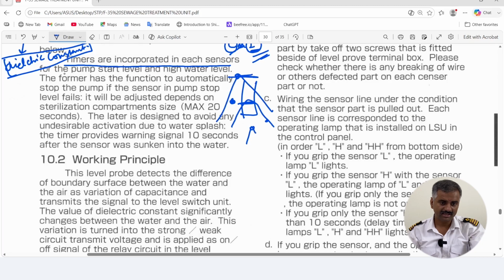To avoid this, pump starting at high level and high water level, the timers are incorporated to start the pump at high level and cut off the pump at low level, to make it automatic. It cuts out within a 20 second period, a maximum of 20 seconds, and it is adjusted as such.